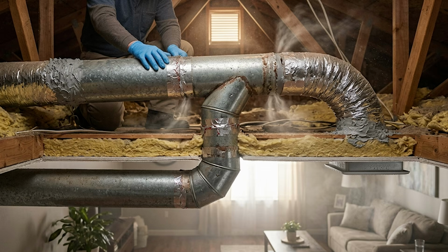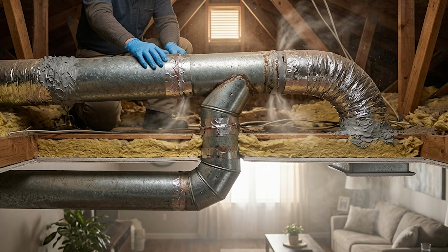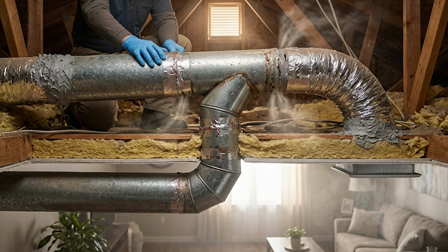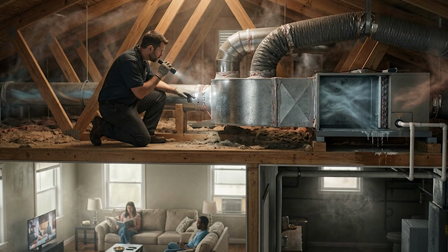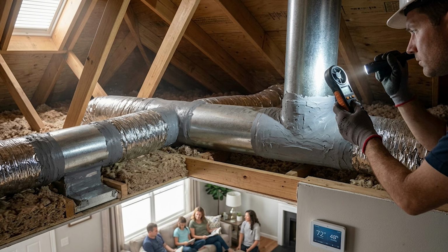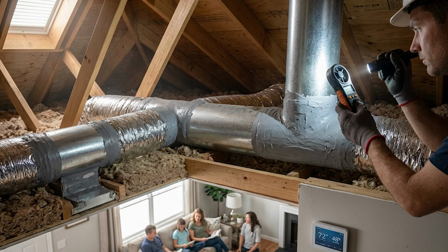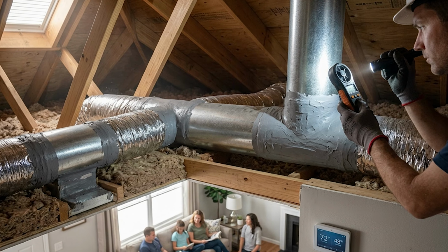When the ducts are leaking, the system is inadvertently pulling in humid outside air. The air conditioner is removing moisture constantly, but it is being replaced just as constantly through the leaks. The temperature looks fine. The humidity never quite gets there. Seal the ducts, and that clammy feeling that has been bothering you for years goes away.